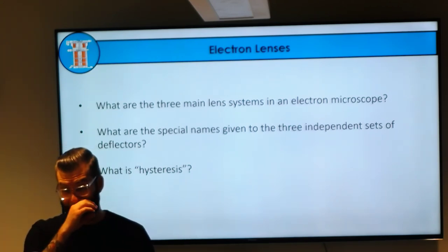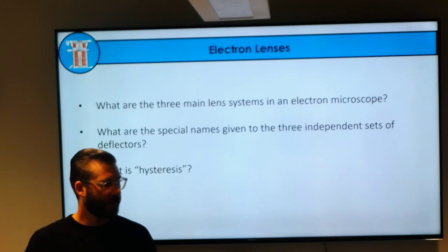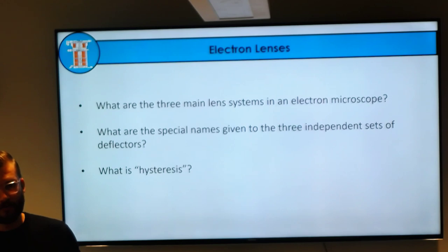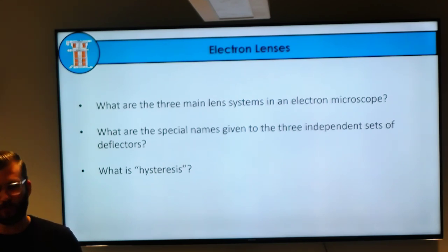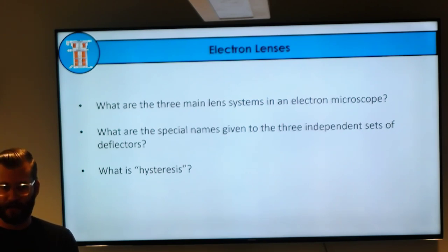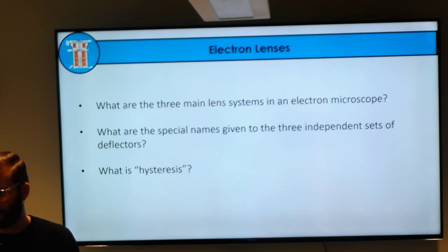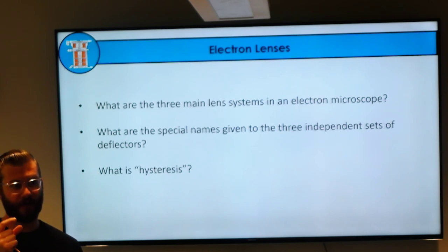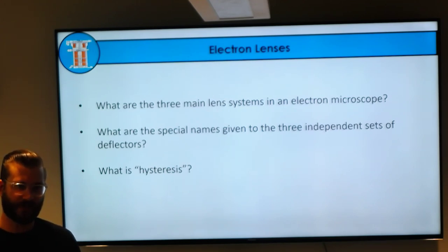Can anybody tell me what hysteresis is? Essentially, the behavior of the lens will change as you change the current moving through it. Each lens remembers the magnification it used to be at. If you're at a really high magnification and go to a low magnification—reducing current or shutting a lens off—then go back to high magnification, it's going to remember that it was at the lower magnification. So you don't go back to the exact same settings. We'll see this memory in the microscope during our practical.